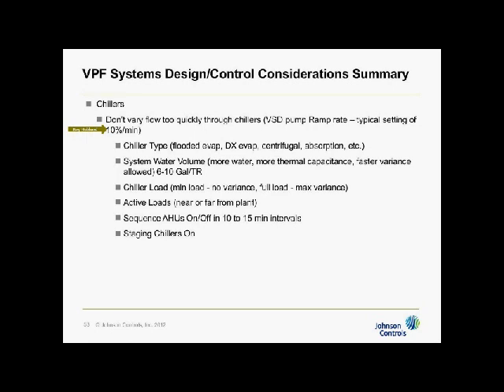Okay? The way you set this is typically in the variable speed pump drive controller. Go to the panel on the pump and look for the ramp function on the variable speed drive. It's usually in seconds to go from 0 to max speed or max speed to 0. It'll be an accel rate and a decel rate, acceleration rate, deceleration rate. It'll usually default to about 60 seconds, which is 100% per minute, far too fast for any chiller. So you just change that to 600 seconds, there's your 10% per minute.